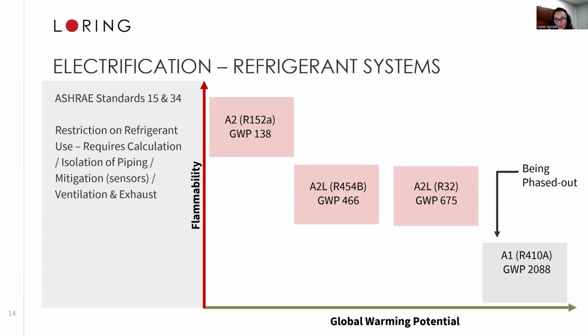Refrigerants, again, as I mentioned, are a great medium, or great material, for exchanging heat, or for exchanging energy and transferring energy within your building. But they do come with the penalty of having a global warming potential, something that, if you're doing an electrification program, you want to pay close attention to, because it's also carbon that's impacting the ozone and impacting the environment. So a very popular refrigerant that you're probably seeing being phased out, or your engineers are telling you is being phased out, is R410.